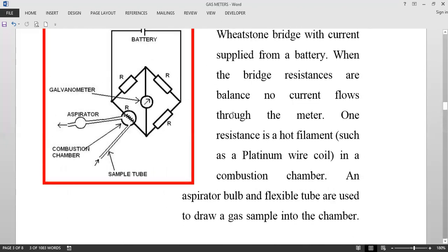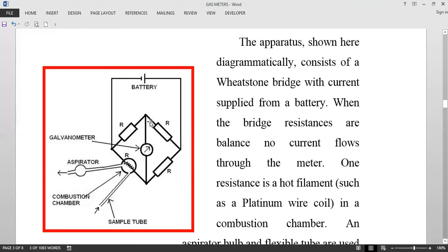To summarize how this functions: it is a Wheatstone bridge with four resistances — R1, R2, R3, and R4. When all four are the same, the bridge is balanced and there is no flow of current. When a sample of gas is withdrawn into the combustion chamber, there is a red-hot filament; the gas burns there and raises the temperature of the filament, which unbalances the Wheatstone bridge. The current flows through the galvanometer, deflecting the needle to show the concentration of gas inside the space.